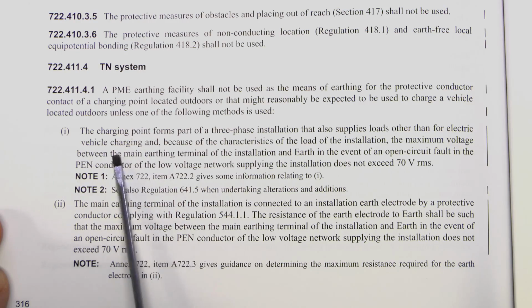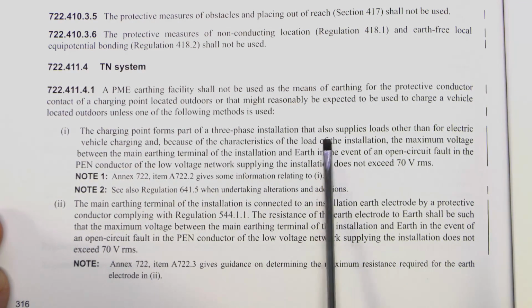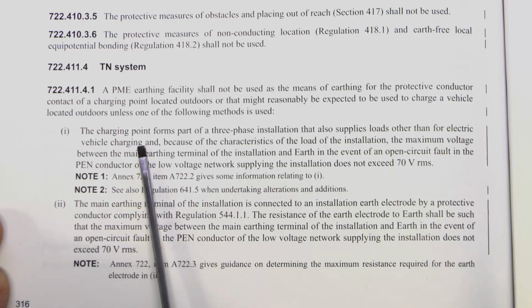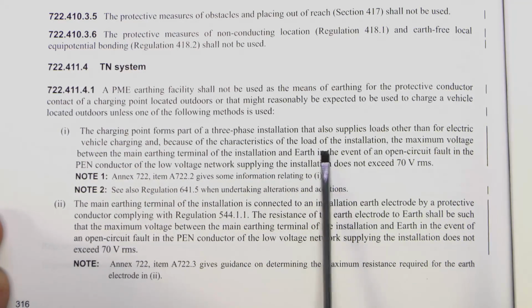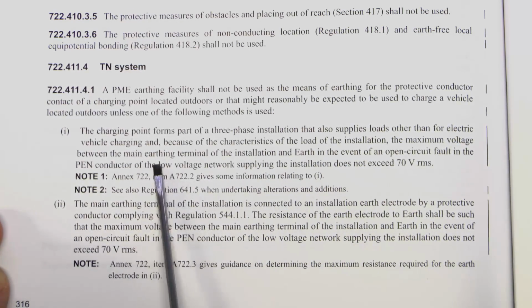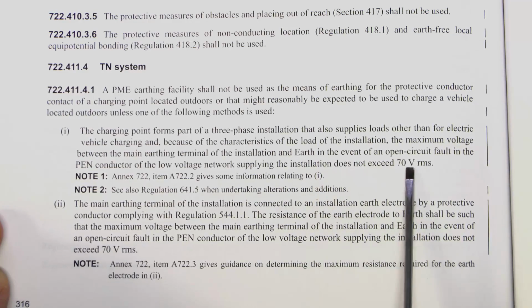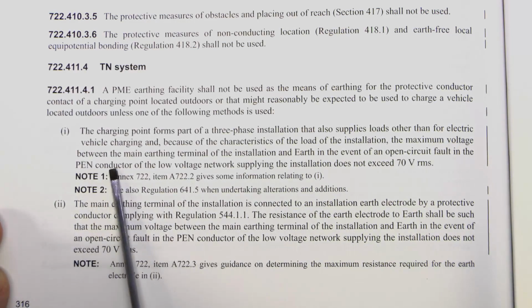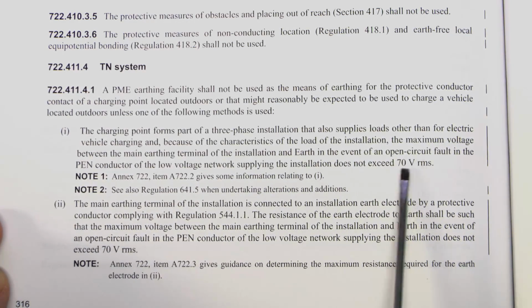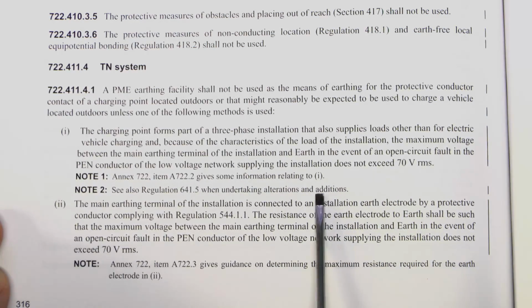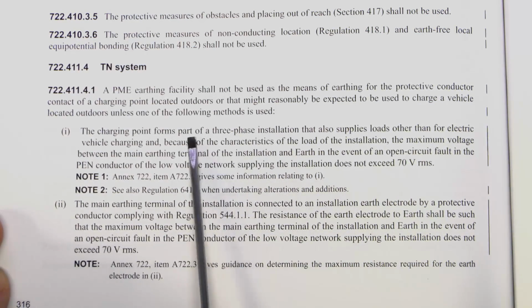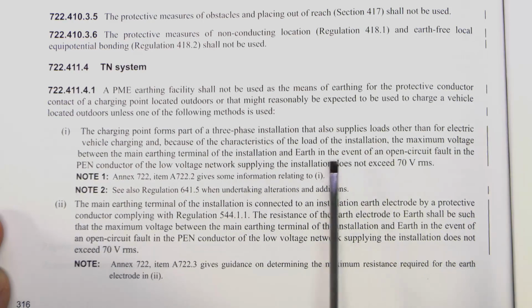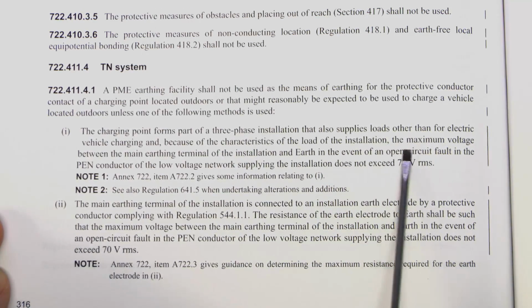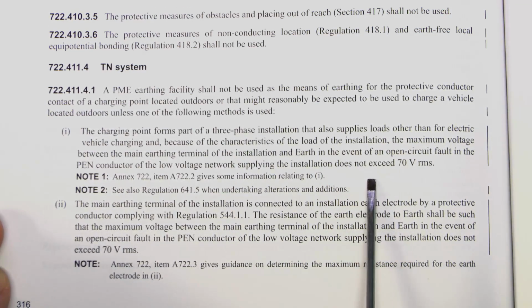So first of all, the charging point forms part of a 3-phase installation that also supplies loads other than for electric vehicle charging, and because of the characteristics of the load installation, the maximum voltage between the main earthing terminal of the installation and earth, in the event of an open circuit fault in the PEN conductor, doesn't exceed 70 volts. That's desperately unlikely in a domestic installation, because first of all, most domestics don't have 3-phase, and even if they did, they're not going to have the other loads, which obviously would make that criterion a possibility.